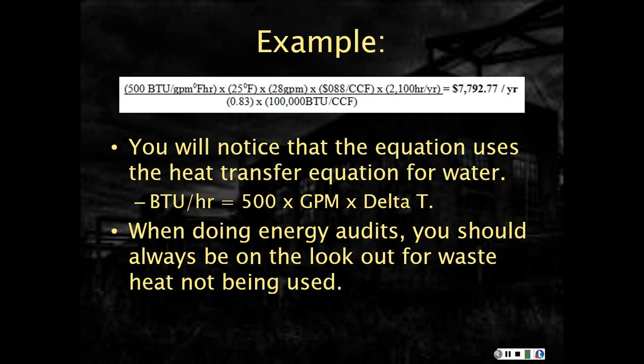And again, it's important to notice that a lot of these hand calculations use formulas that you're already familiar with. Another heat transfer formula. This one happens to be for fluid flow of water. This will work with other fluids. You just can't use 500. You have to use whatever that constant is for that particular fluid. The other thing, when doing energy audits, is you should always be on the lookout for waste heat not being used.